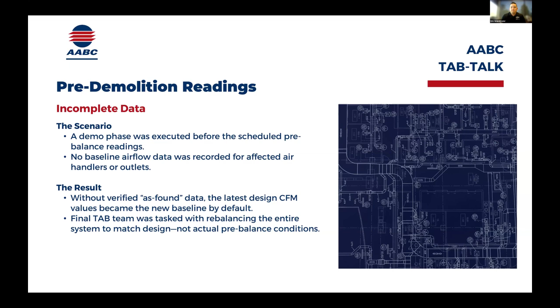Just real quickly, guys, just don't assume. Don't assume any kind of operation of equipment when you're doing pre-balances. We had a situation once again in a hospital where they needed to increase return airflow in one particular space. We went there. The MEOR had asked us, hey, can you ensure that we can get this return air out of this one diffuser? It was like an increase of, I think, 80 to 85 CFM.